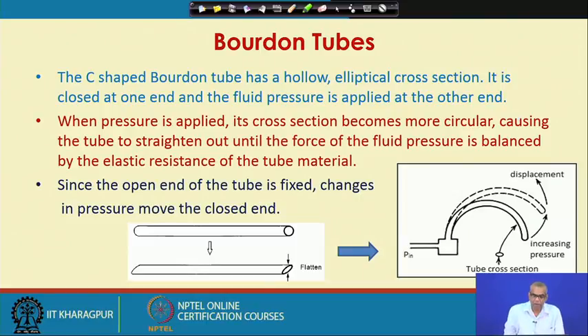So, when pressure is applied, its cross section becomes more circular, causing the tube to straighten out until the force of the fluid pressure is balanced by the elastic resistance of the tube material. That is why this is known as an elastic element. Since the open end of the tube is fixed, changes in pressure move the closed end, and the displacement of the tip of the Bourdon tube is a measure of the amount of pressure that is being applied inside the Bourdon tube.